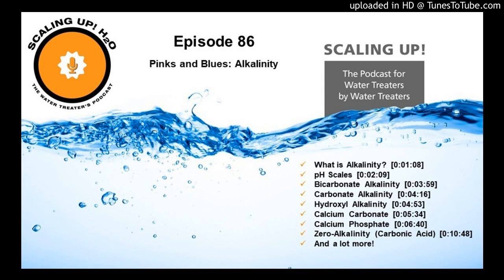So with carbonate alkalinity, the reagent that you use to test for that is phenolphthalein. Phenolphthalein is a reagent that will only turn pink at a pH of 8.3 or above. Well, let's look at that. I said that carbonate alkalinity only exists at a pH of 8.3 or above. So how cool is it, we have a pH sensitive dye that we can measure the pH, and that tells us how much carbonate alkalinity we have.